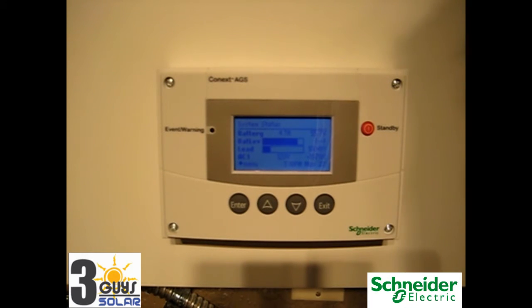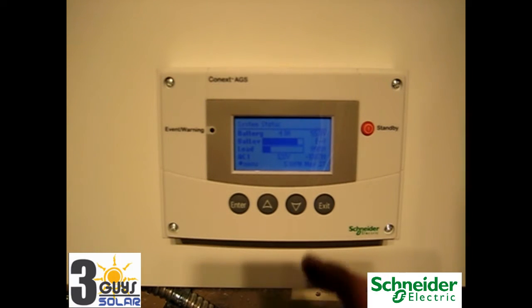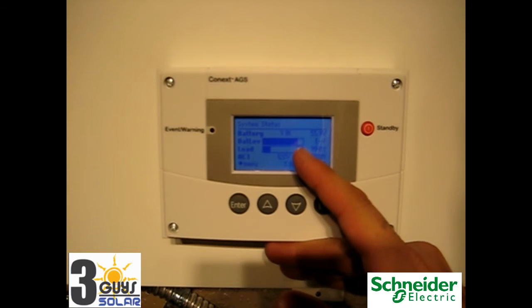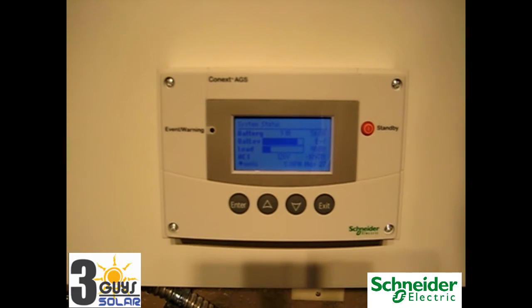It is a 48 volt battery bank, nominal voltage, but the batteries are basically at 98%, 95% fully charged, and our battery voltage is high. Plus the system is set to sell, so everything above a specific voltage will be taken right off the top and sold into the grid. Currently we have 4.6 amps of energy going into the batteries.